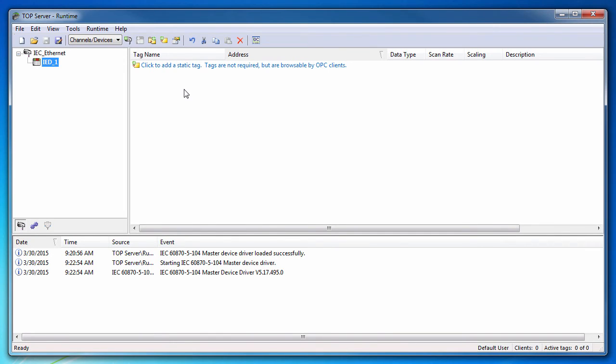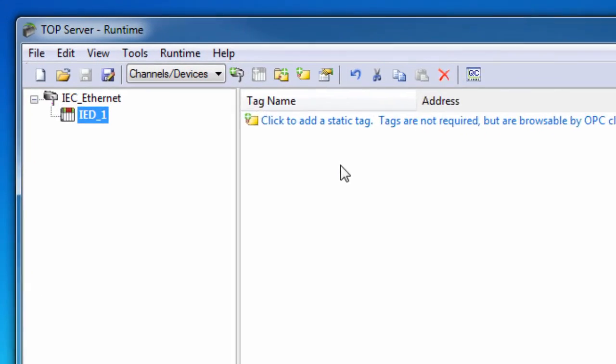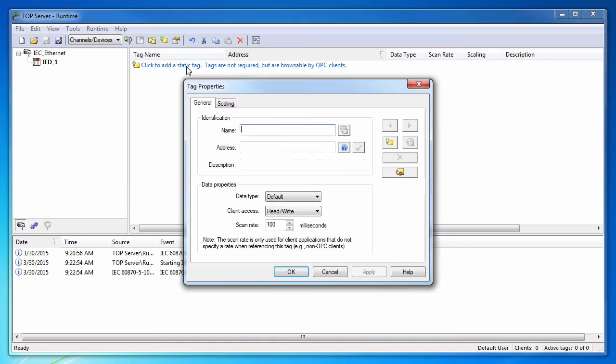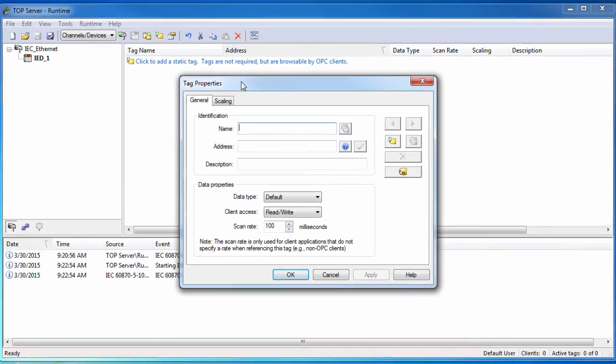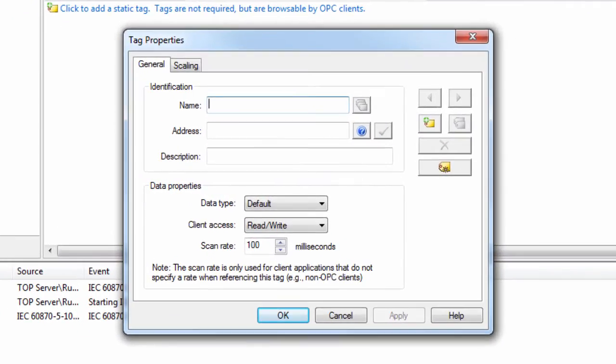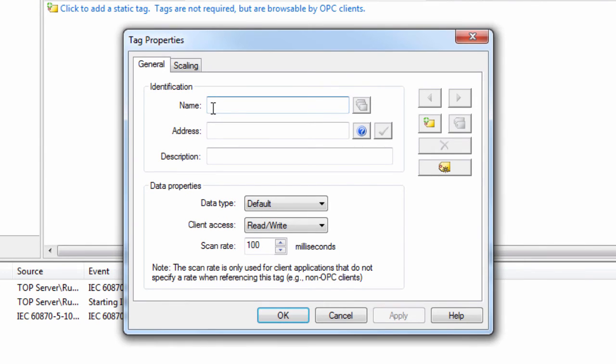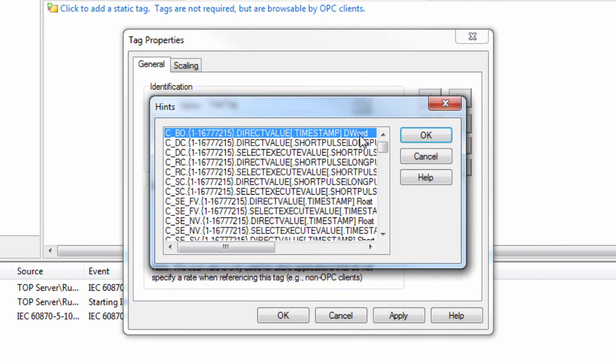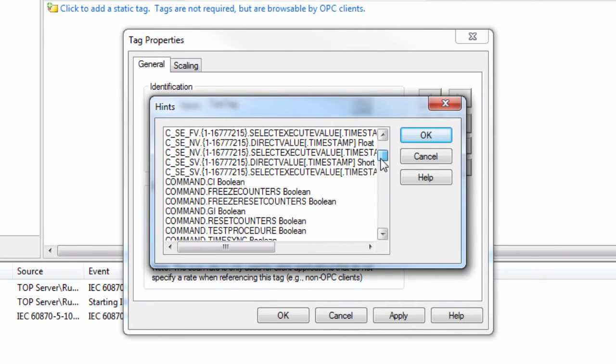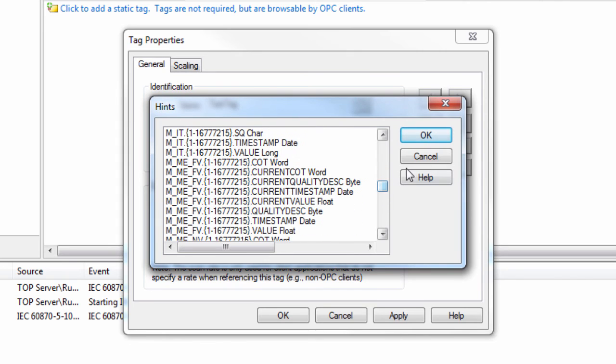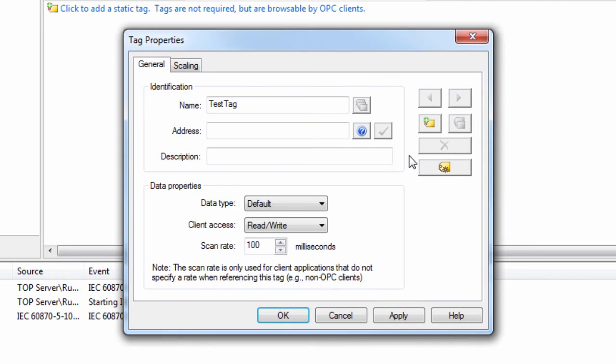Tags can either be accessed dynamically from your client application or using static addresses in the server. To create a static tag in the server, click to add a static tag. Give the tag a friendly meaningful name and enter the desired address. If you need help determining the correct address and format, click the Hints button. This will provide you with the address formats compatible with the server. You can add an optional description for the tag if desired.